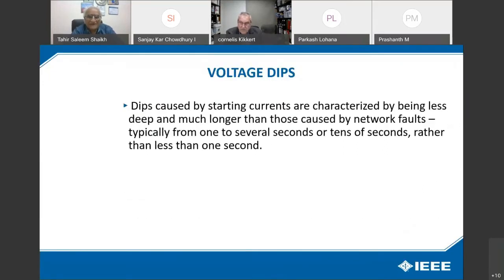Dips caused by starting currents are characterized by being less deep and much longer than those caused by network faults, typically from 1 to several seconds, or tens of seconds, rather than less than 1 second.